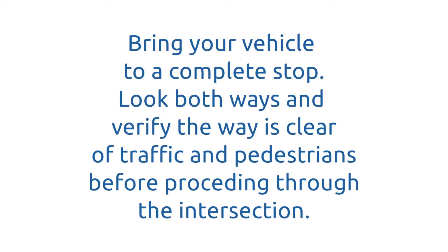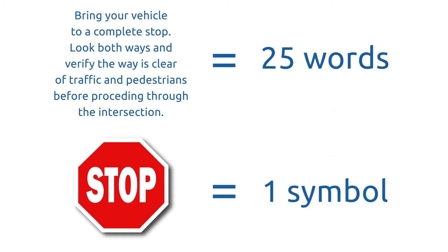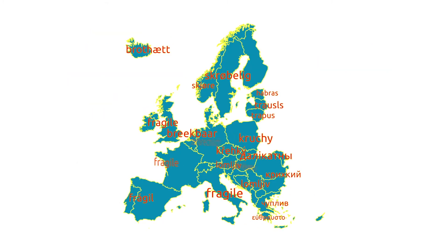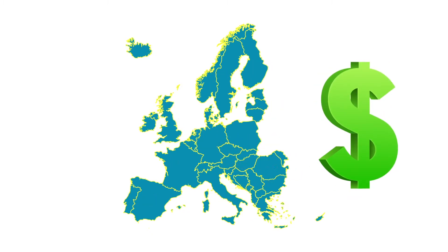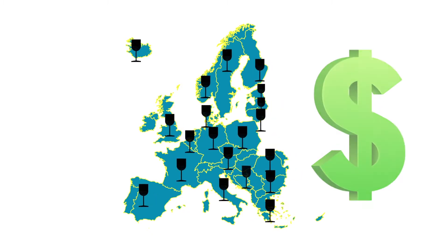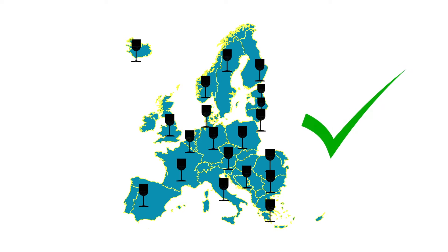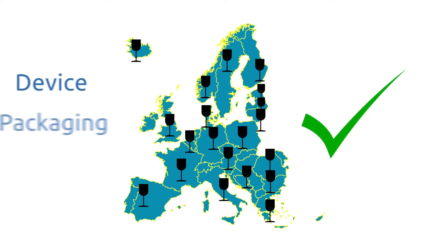There's a very familiar saying: a picture is worth a thousand words. This holds true in the medical device industry. In fact, a picture is worth more than words — it's worth money. There is a significant expense involved in translating text. In the EU alone, there are over 20 official languages, and all of those words take up valuable real estate on the label and packaging. Symbols apply to all devices in many markets worldwide, and can be used on the device, on the packaging, and the instructions for use.